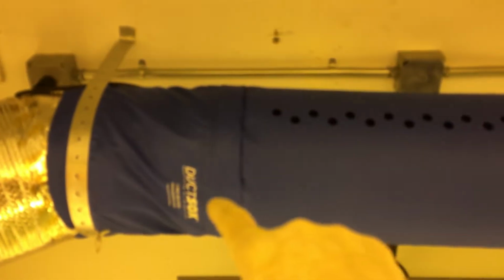Now they went to this company and said, we want our ducting done with air socks. So they got air socks. And they said, oh, this is engineered. These are engineered to give us all the cooling we need. Now this is only a 16-foot sock. And out of the 16 feet, about 15 feet of it has these little tiny holes, out of a 5-ton system.